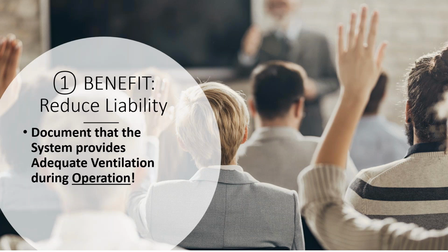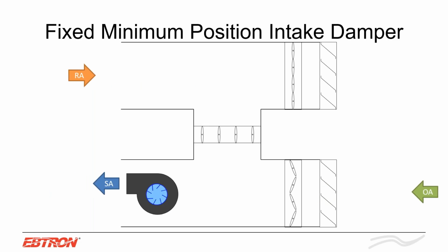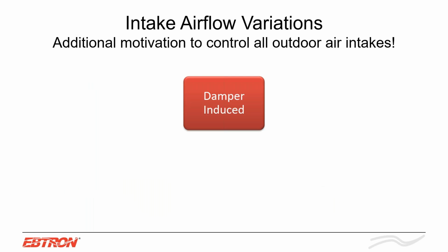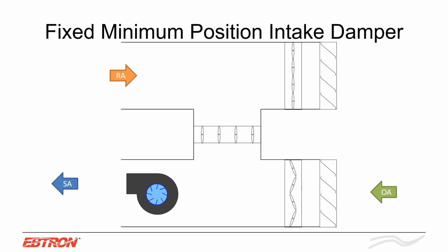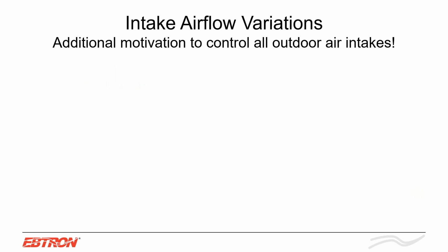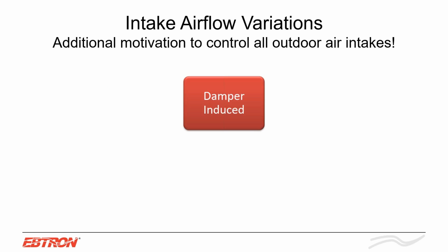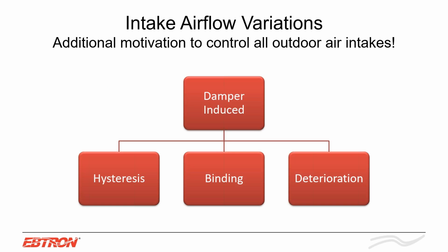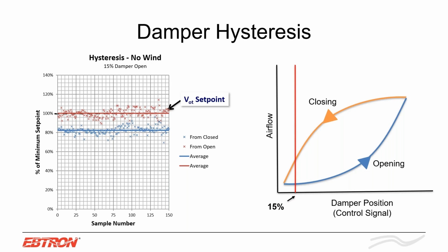So let's look at some of these outside factors and show why you really need to measure. Let's look at a fixed minimum position intake damper. This is just a recirculating air handling system right here. And dampers have issues, just like other equipment. It's always good to use a high quality damper. But for the issues that dampers see, you have hysteresis, you have binding over time, or you may have deterioration in the seals. So we did a simulation at our factory, and this is looking at going from 0% to fully open, back to 15%.